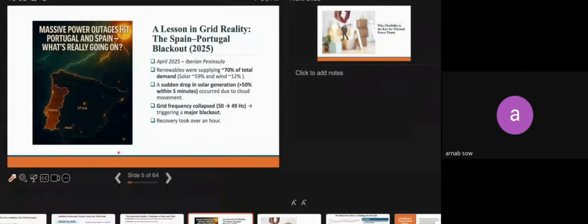A sudden dip in solar power, greater than 50% within 5 minutes, occurred due to cloud cover, which caused the grid frequency to fall from 50 to 49 hertz and led to cascading tripping of the relays, causing grid failure. As we move toward 500 gigawatt of renewable energy, such fluctuations will become more common. So as the major shareholder in the Indian energy mix, thermal power plants must become more flexible and capable of fast response to handle these fluctuations.